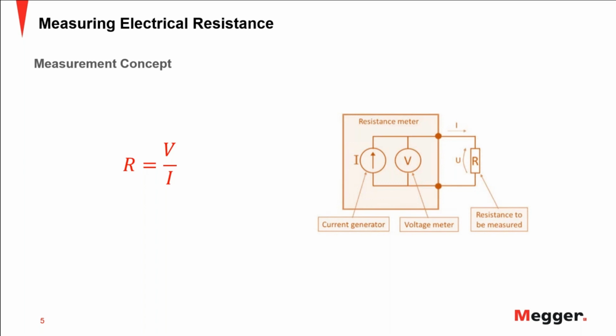So this is showing the setup, or the diagram, for a low resistance measurement. You see that there's a current generator, there's a voltmeter, and you have the object under measurement represented by the R there. And as you can see, there's going to be a current circulating, and there's going to be a voltage drop across the resistance. And those two parameters are the ones that you use to calculate.